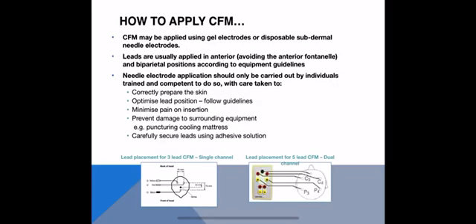So how do we apply CFM? CFM can be applied using gel electrodes like ECG leads, or disposable subdermal needle electrodes. The leads are applied in an anterior or biparietal position — basically placed on the sides of the head — according to the specific guidelines for the equipment being used. Some CFM equipment requires three leads; others require five, depending on the equipment.